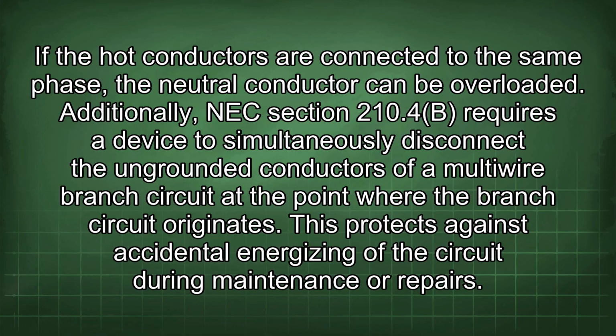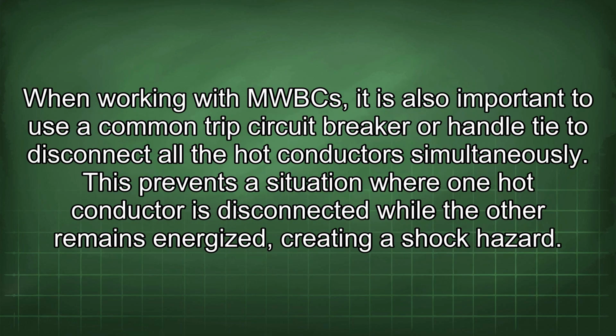Additionally, NEC section 210.4(B) requires a device to simultaneously disconnect the ungrounded conductors of a multi-wire branch circuit at the point where the branch circuit originates. This protects against accidental energizing of the circuit during maintenance or repairs. When working with MWBCs, it is also important to use a common trip circuit breaker or handle tie to disconnect all the hot conductors simultaneously. This prevents a situation where one hot conductor is disconnected while the other remains energized, creating a shock hazard.